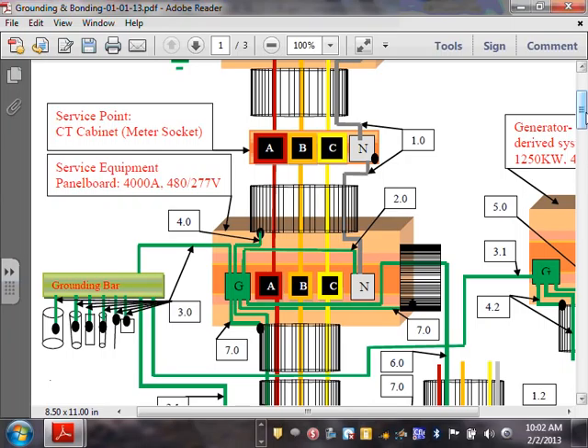And then right to this bar, I bring, let's assume this one was my water pipe, tie into it again with a grounding electrode conductor. Then I go to, let's say this is a ground rod. This is the steel of the building. This is a wire, like a wire ring or ground ring. This guy is supposed to be a ground plate.